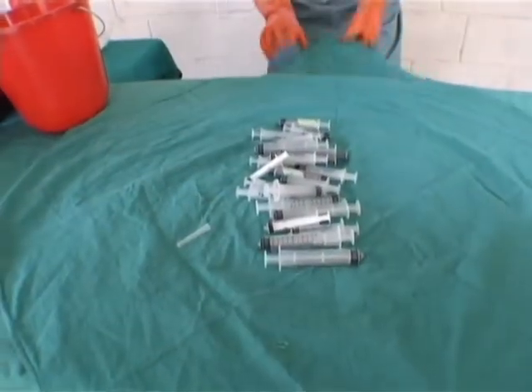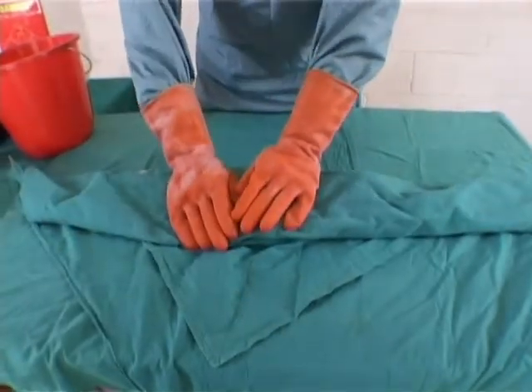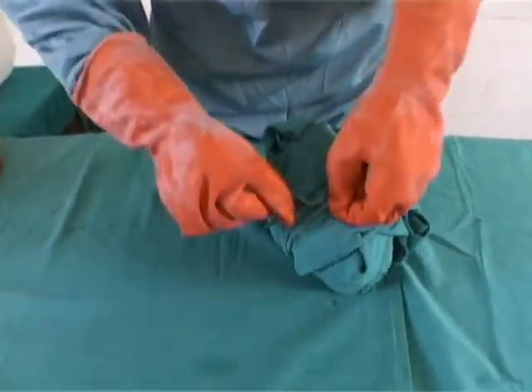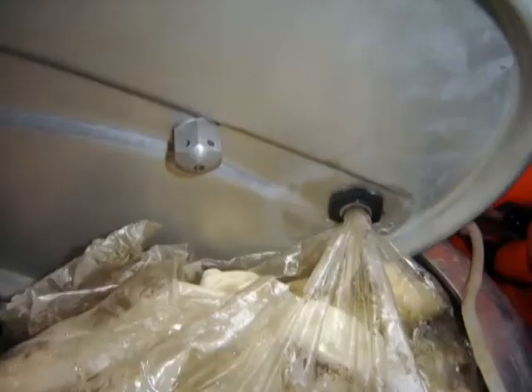Ideally, you should use a heavy-duty cotton cloth with a tying cord attached. It's very important for safety reasons that this bundle be secured and tied before inserting it into the autoclave. Do not use this cloth for any other purpose, and do not use plastic wrapping of any kind.